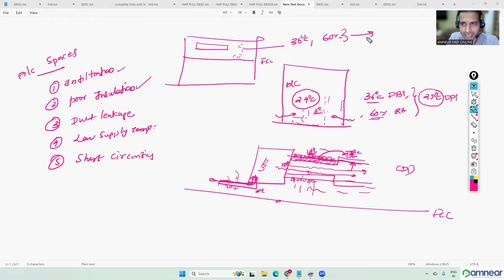Correct. So this is cold air only, at a temperature of 13 or 14 degrees Celsius. When this 14 degree air comes into contact with the unconditioned air above the false ceiling, condensation can come, because the dew point temperature above the false ceiling is 27 degrees Celsius, and the air leaking from the duct is at 14 degrees Celsius. So when this 36 degree, 60% air touches the 14 degree air, definitely condensation can come there. Water will accumulate on the ceiling, and the ceiling may fail. That's why poor insulation is a reason for condensation. Even duct leakage is the same; duct leakage is air leakage only.